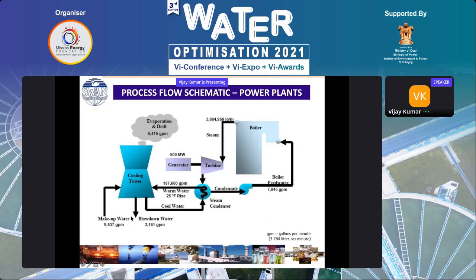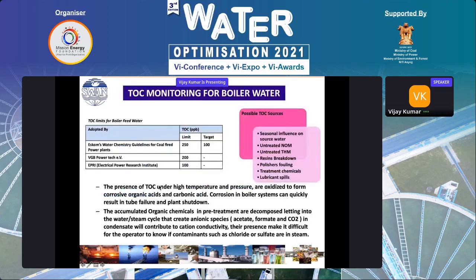So the cooling tower water is pumped inside the condenser tubes to the cooling tower to reduce the temperature. The temperature picked up here comes down and cools down back here. So this is one cycle. In these cycles, TOC in boiler water is very, very dangerous. We are talking about the limits given by EPRI and Eskom, 100 ppb to 250 ppb.